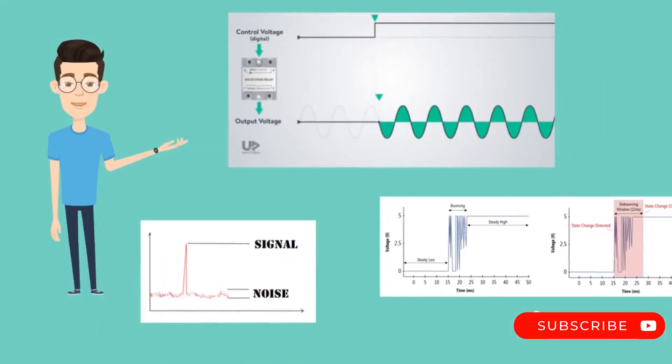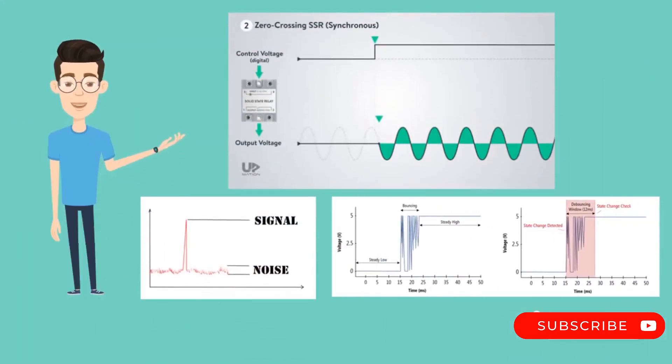One of the biggest advantages of solid-state relays over an electromechanical relay is its ability to switch off AC loads at the point of zero load current, thereby completely eliminating the arcing, electrical noise, and contact bouncing associated with conventional mechanical relays and inductive loads.